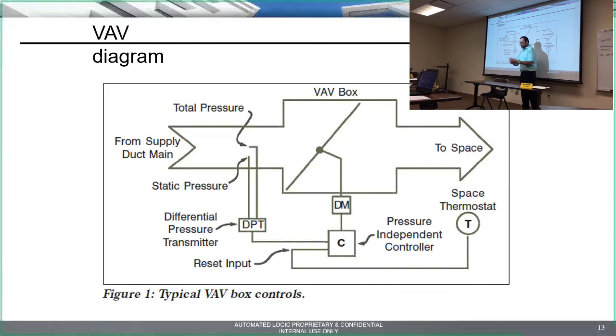So static pressure, I always refer to it as bursting pressure. If you can imagine in your head, when the pressure is in, it's forcing out on the ductwork. So as you're pushing more air through the ductwork, it's causing pressure to push out on the ductwork. Does that make sense? Total pressure has static pressure because it's pushing out, but it's also the pressure that's going directly into the tube. It's the inlet of that tube and it's going straight into the inlet of the tube. So this pressure is more than this pressure.